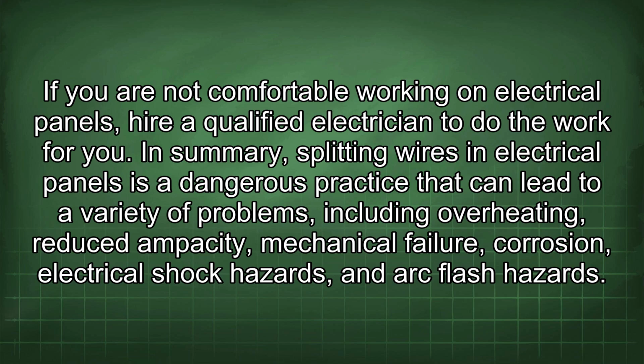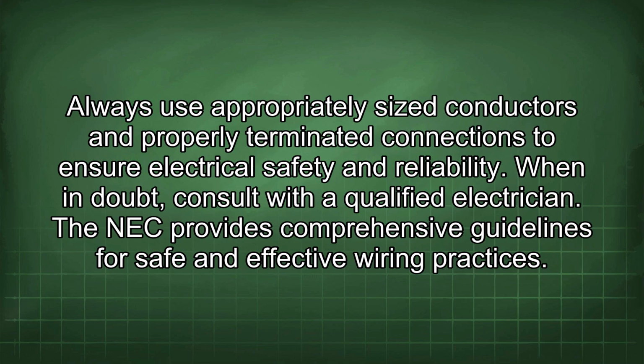In summary, splitting wires in electrical panels is a dangerous practice that can lead to a variety of problems, including overheating, reduced ampacity, mechanical failure, corrosion, electrical shock hazards, and arc flash hazards. Always use appropriately sized conductors and properly terminated connections to ensure electrical safety and reliability. When in doubt, consult with a qualified electrician.